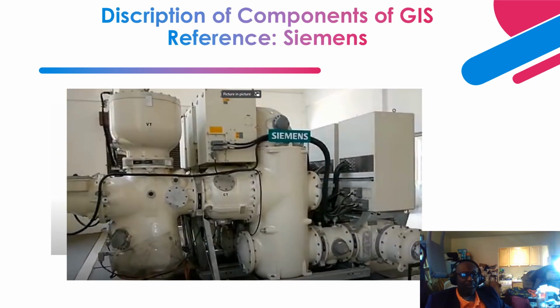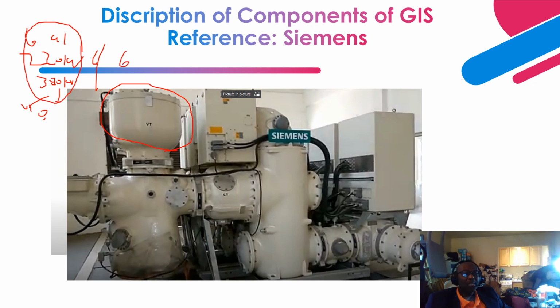Now, let's go through this typical Siemens GIS. As you can see over here, this is a picture of the voltage transformer. Let's say you have a bus voltage, a primary side voltage of 220 kV, or 300 kV, or up to 800 kV. But this one looks like 69 kV. This VT basically steps the voltage down from this high voltage to 69 volts, line to neutral or line to ground, or 115 or 120 volts, line to line, to be used by protection relay elements or metering elements.